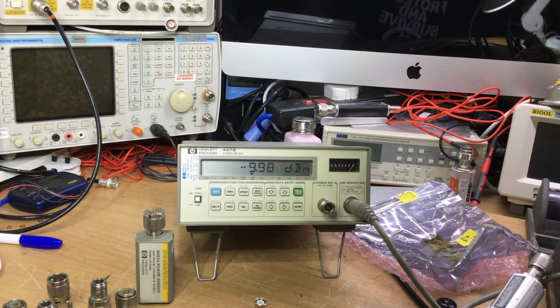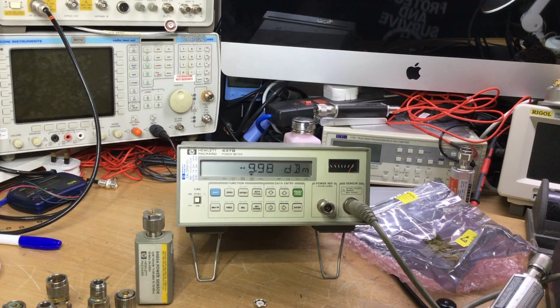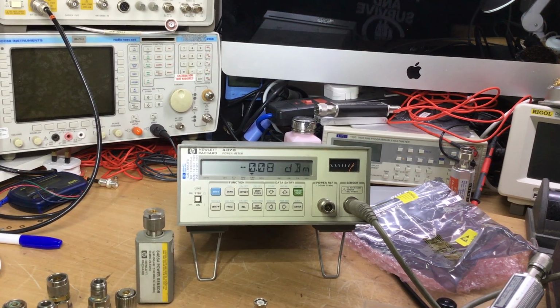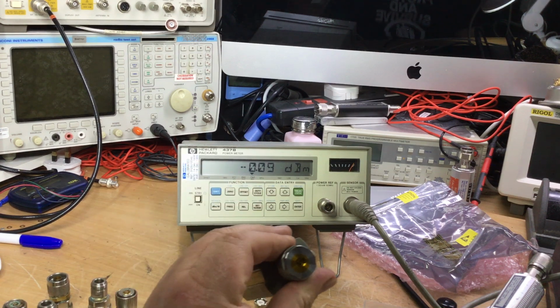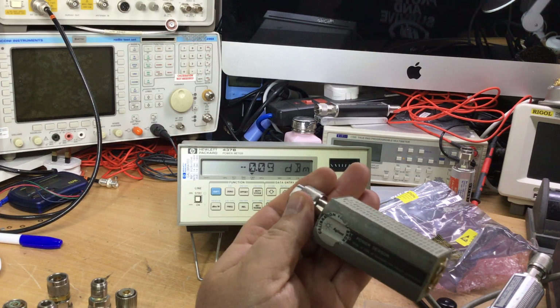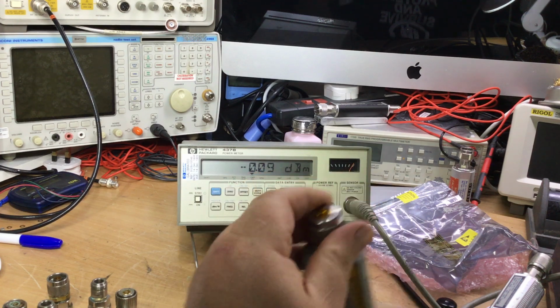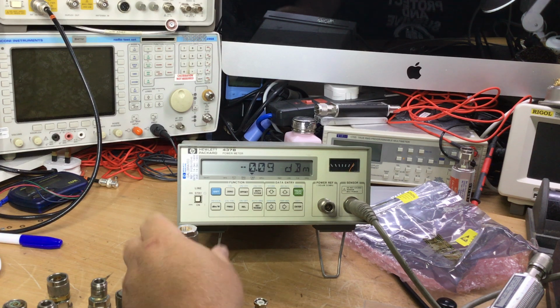Obviously, if I put the power back to 0 dBm, then we jump back, and obviously if I turn the RF power off, then we revert back to the noise floor of a sensor, then re-establish the RF power, and then we're back again. So, you know, it's reading accurately, is that sensor, there's no problem there. Can't see there being an issue with that. So at least that proves that particular sensor works okay. So I think it's just a case now of testing this sensor the same, and fingers crossed it'll be okay for him. So right, onwards and upwards.